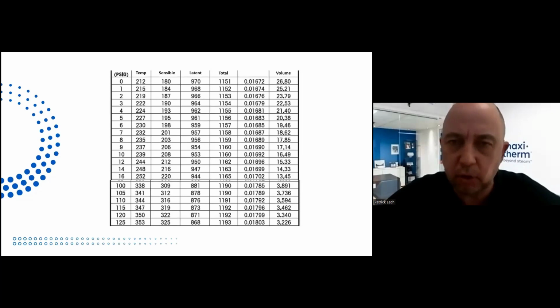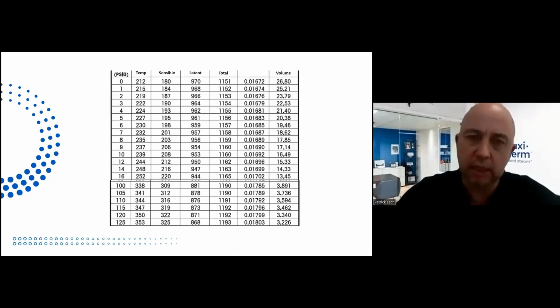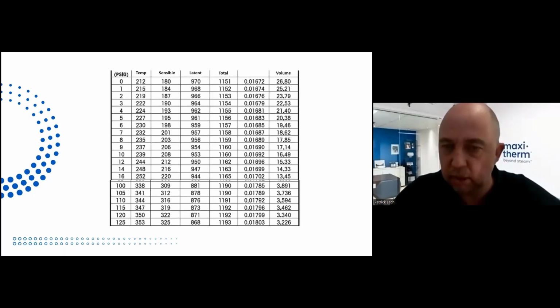So this is the steam table on ASHRAE book. I just want to pay attention again, recall on that video that you watched. So as higher steam pressure we're going, temperature of the steam is going higher. Latent heat, the change of phase of 1 pound of steam that turns 1 pound of condensate, it's going down, right? And then the volume of the steam goes drastically down. So that explains why most boiler rooms work at high pressure steam, it's a question of transport. And then we knock down the pressure because latent heat is higher and temperature is lower and it's easier to control. Sensible heat, though, it's going higher.